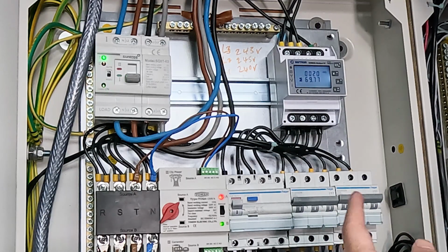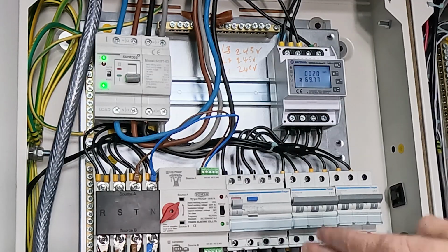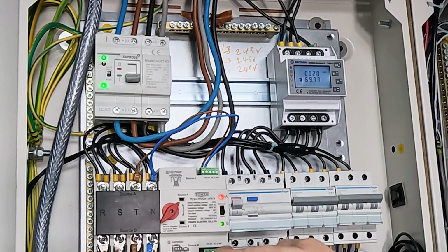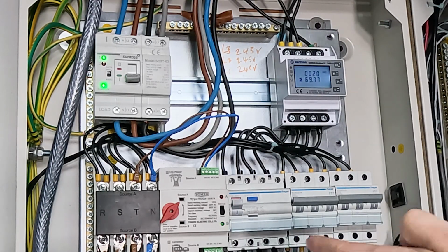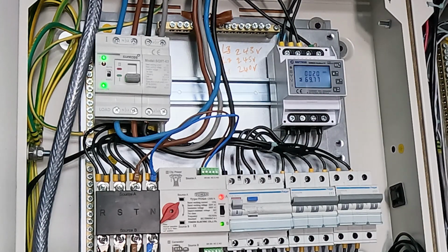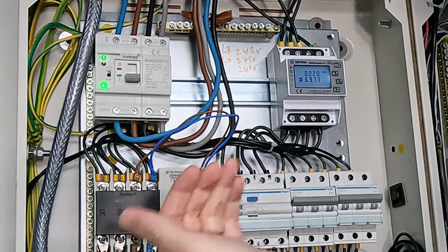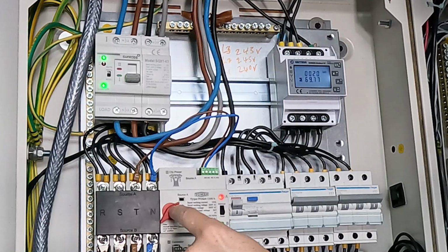Then the inverter ups that voltage to 230, or your set point, and then this thing will start doing the transfer after 20 milliseconds, and it takes 8 milliseconds to do it, which is extremely quick, but it adds those two delays together. So 20 milliseconds plus the 8 milliseconds will actually cause something like your meter to turn off, and possibly your desktop computers. So I would highly recommend setting the output of your inverters to source A so that the default state is A.